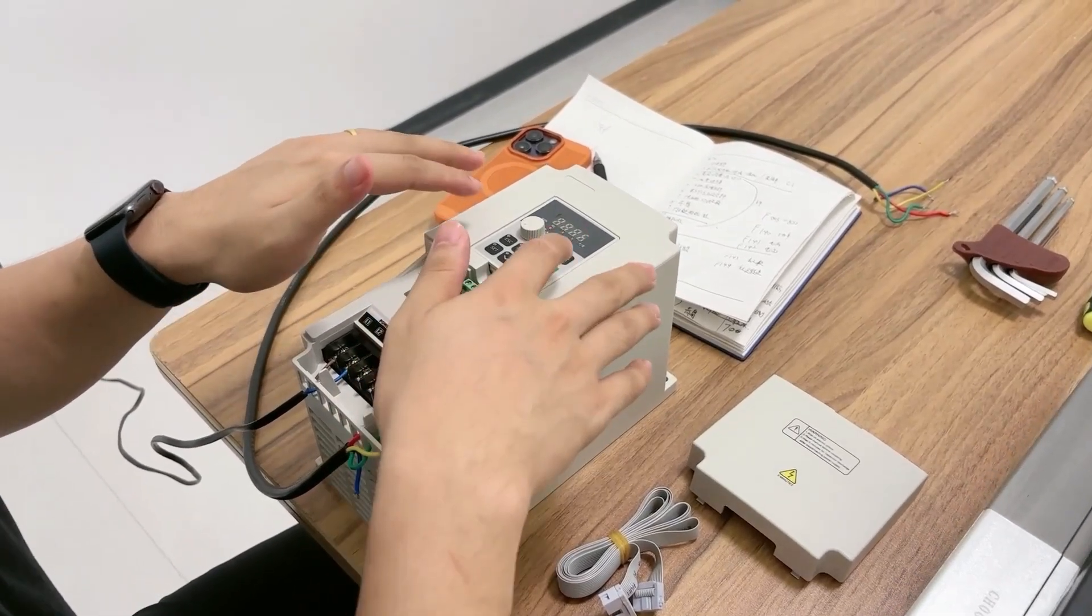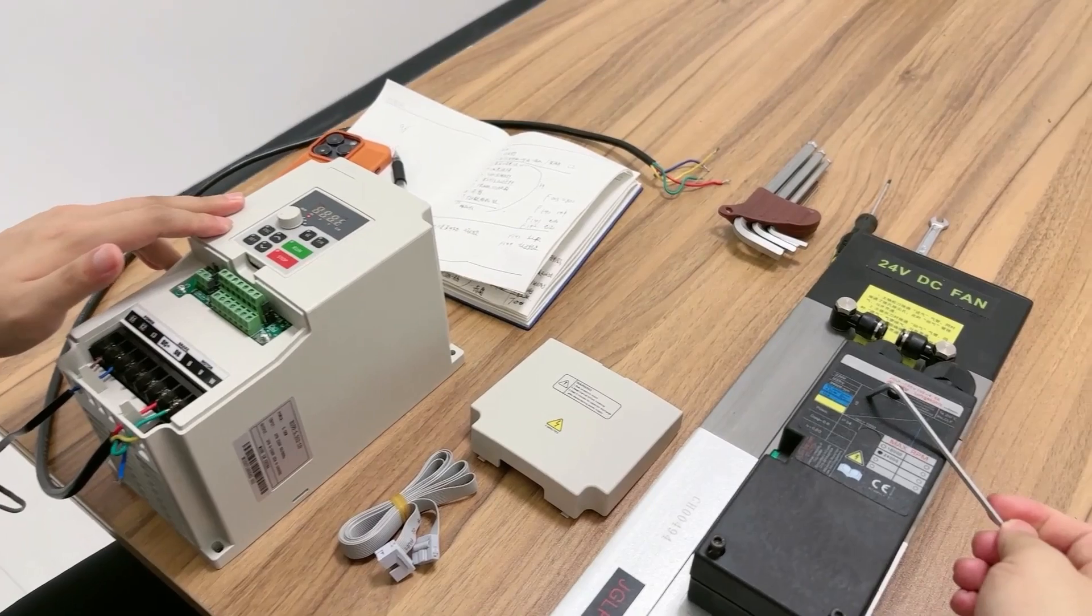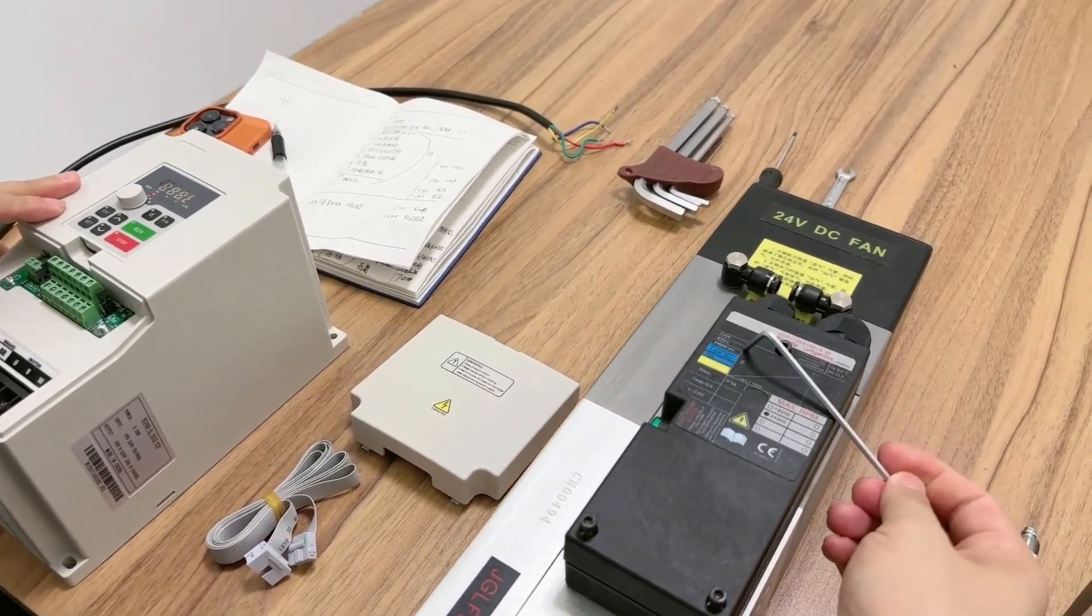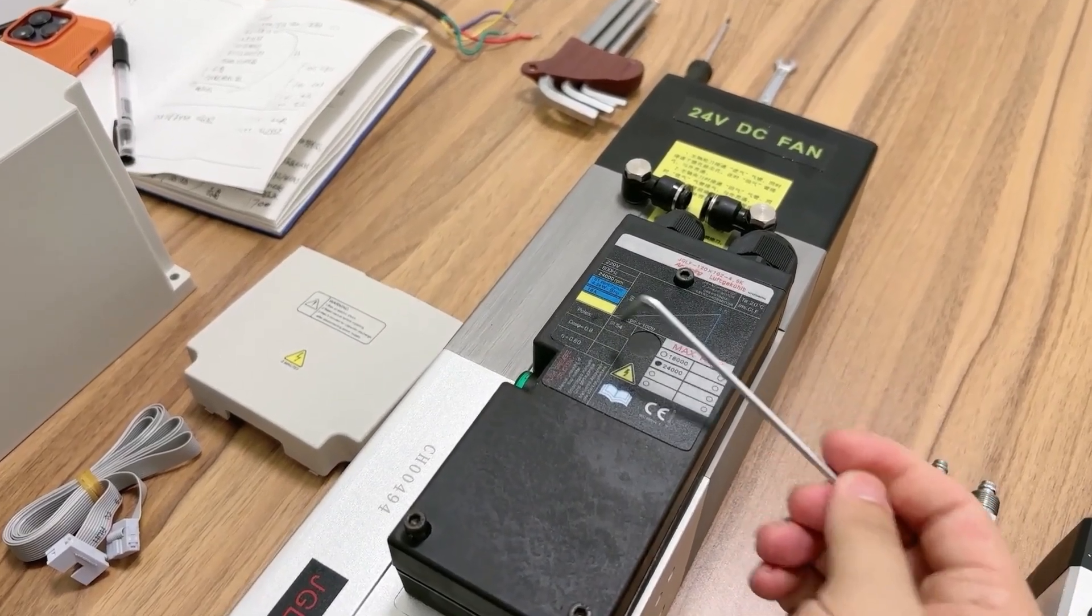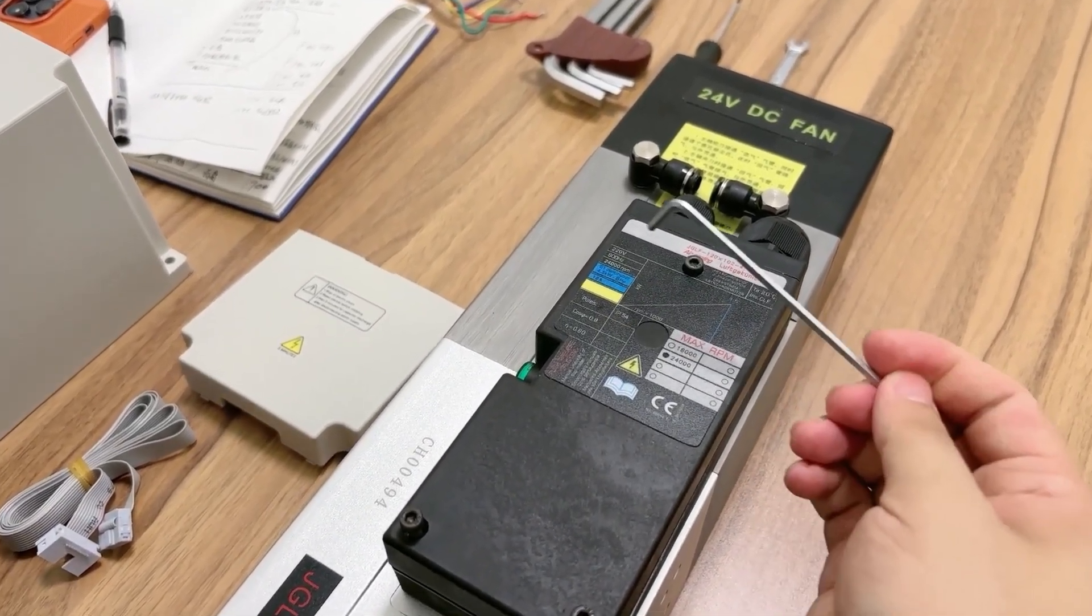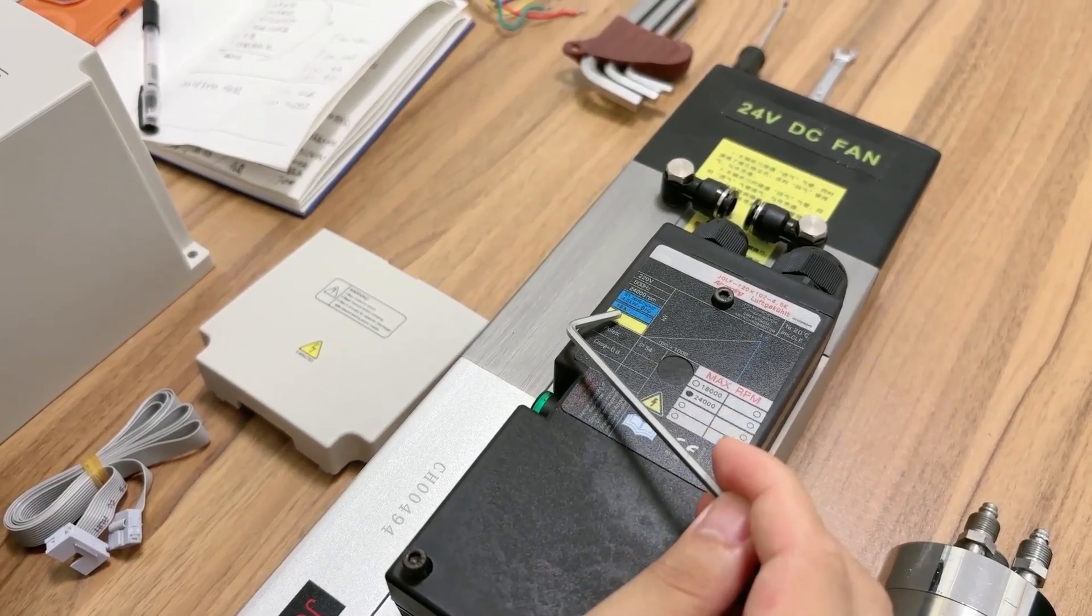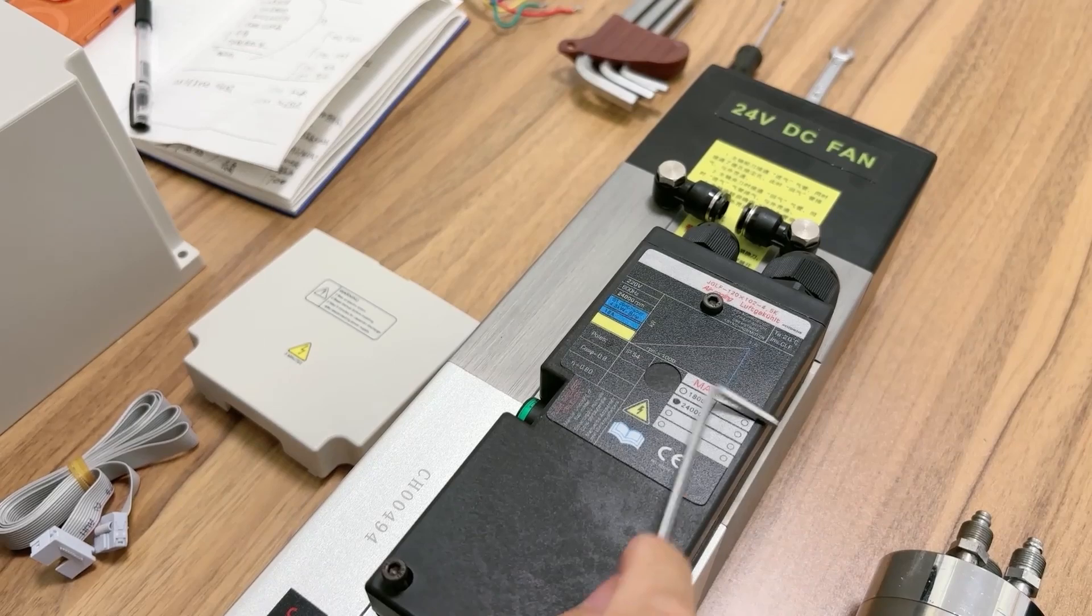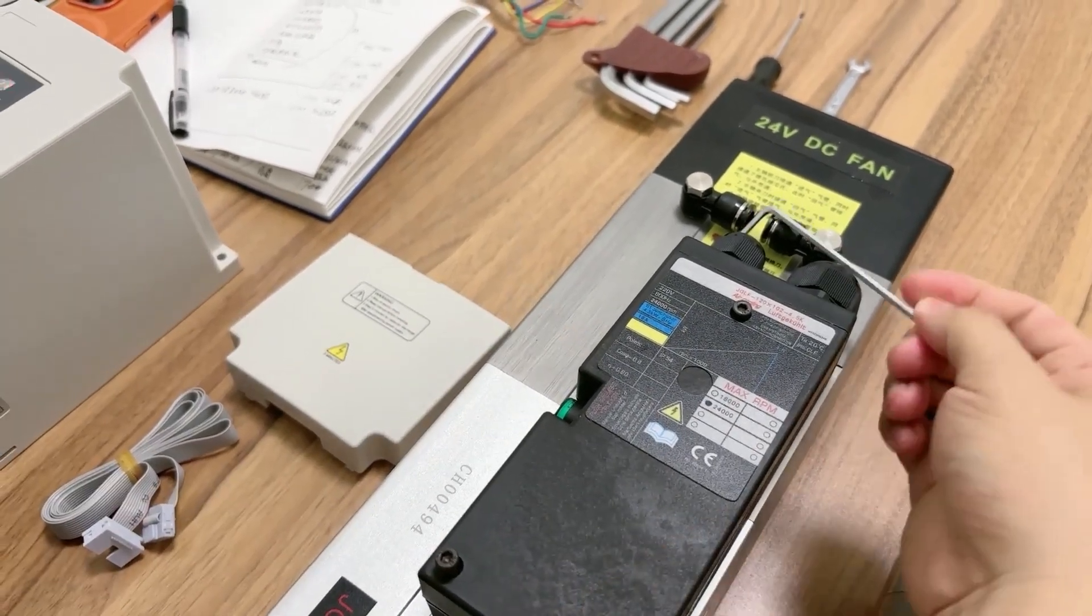Before we run the spindle, we need to set the parameters according to our spindle's specifications like frequency, speed, and poles. This one is four poles and it has a current of 16 amps. These are the main specifications that need to correspond with our VFD.